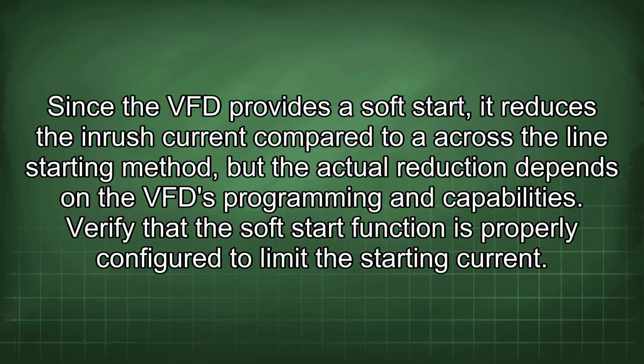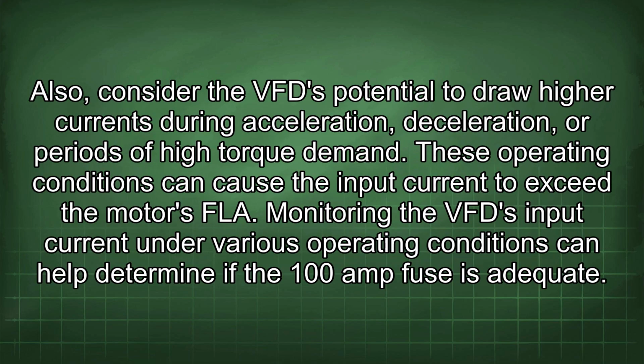Since the VFD provides a soft start, it reduces the inrush current compared to a across-the-line starting method, but the actual reduction depends on the VFD programming and capabilities. Verify that the soft start function is properly configured to limit the starting current. Also, consider the VFD's potential to draw higher currents during acceleration, deceleration, or periods of high torque demand. These operating conditions can cause the input current to exceed the motor's FLA.